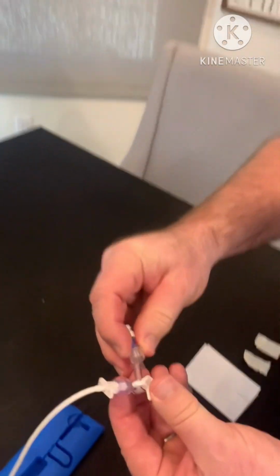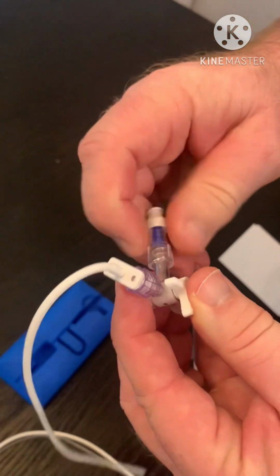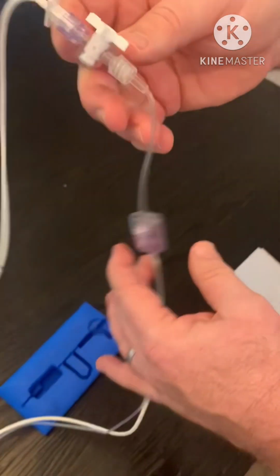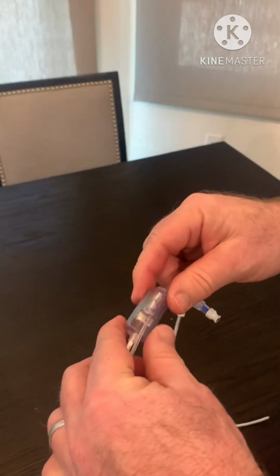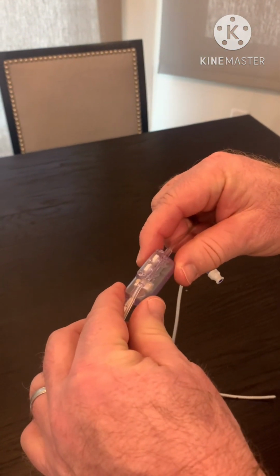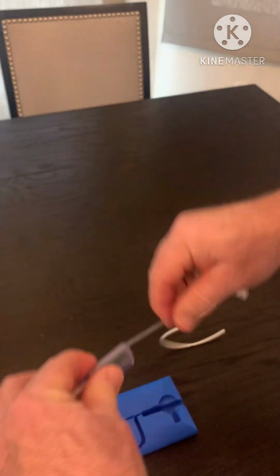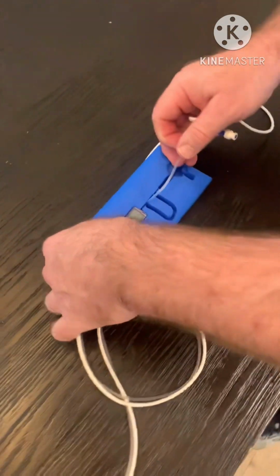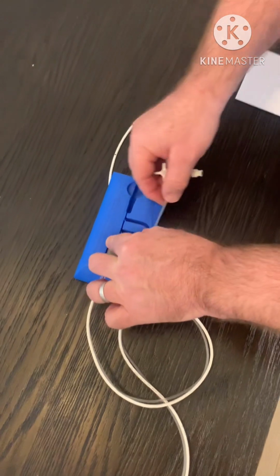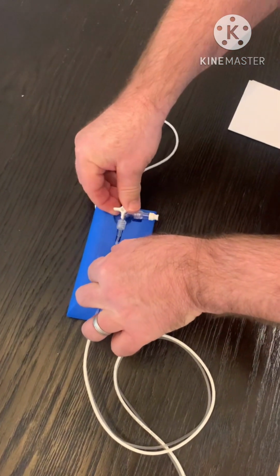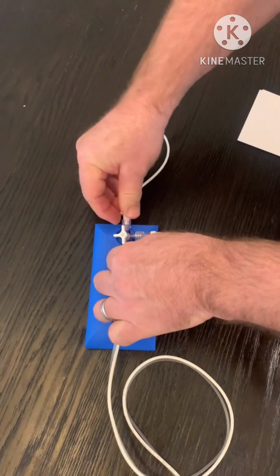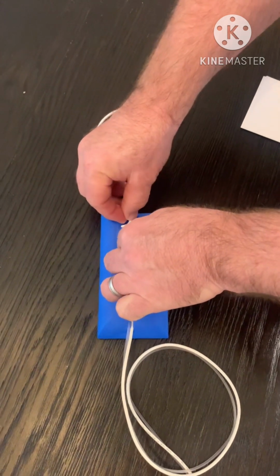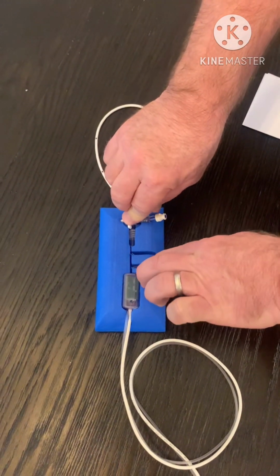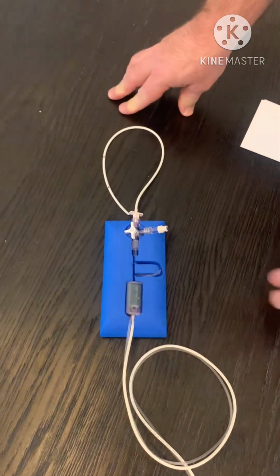Now that the tube set is effectively loaded into the machine, the surgeon can take the Smartsite for sampling and apply it onto the 3-way. Then you want to find the transducer, which is triangular shaped, find the point, and put it down in the pad. We wrap the tube set into the LiquoGuard pad, and now we're ready to apply it onto the patient.